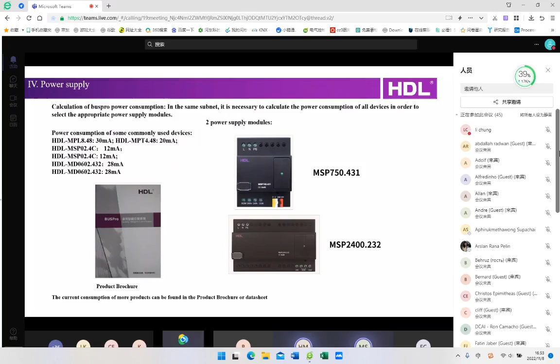For example, if you have so many devices, when you add up the power consumption and find their amperes will exceed 70% of the power supply, then please add another power supply. Because if the total consumption of the devices exceeds 70% of the power supply module, the system will not work properly. So please don't do this.